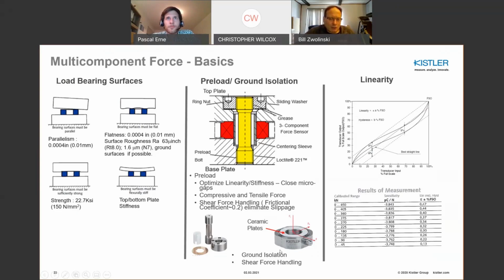The 3-component force sensors also have a ceramic top coating, which provides ground isolation, and also the increased frictional coefficient that I mentioned of 0.2. So that absolutely complements high shear force handling solutions. I mentioned linearity. Linearity is basically the plot of input force versus output force. The straighter that line through the origin, the better the linearity. So you always want to be sure that the preload gives you the best linearity out of the sensor. I show here also you can do partial range linearity on any force sensor.